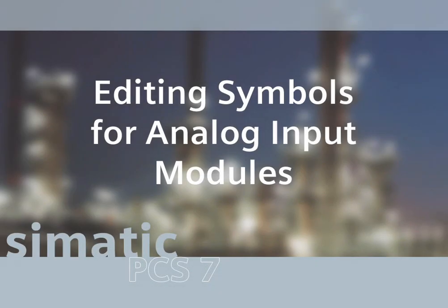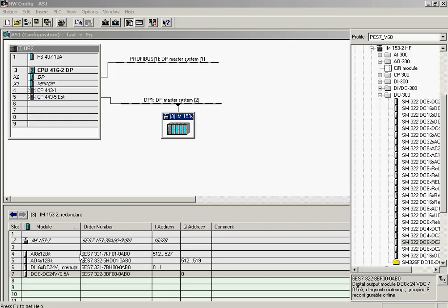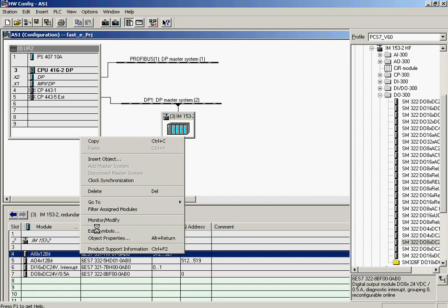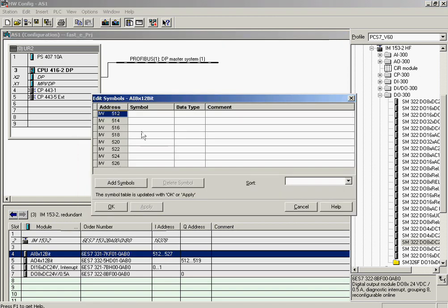In order to use symbolic addressing of I/O throughout the configuration, instead of rack slot channel numbers or memory locations, each address is given a unique symbolic name and comment in the Edit Symbols dialog. The Edit Symbols dialog is activated to enter the symbols. The symbol name PVIN of controller 1 is entered in the first line as well as in the comment column, done by copying the symbol name to the clipboard and pasting it into the comment field.